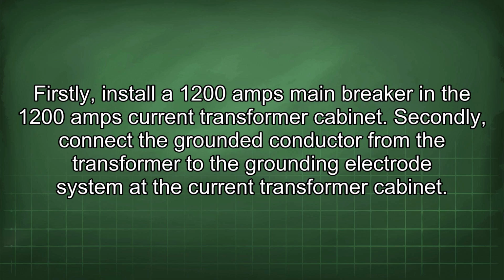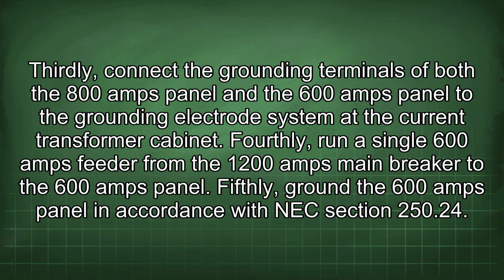Secondly, connect the grounded conductor from the transformer to the grounding electrode system at the current transformer cabinet. Thirdly, connect the grounding terminals of both the 800 amps panel and the 600 amps panel to the grounding electrode system at the current transformer cabinet. Fourthly, run a single 600 amps feeder from the 1200 amps main breaker to the 600 amps panel.